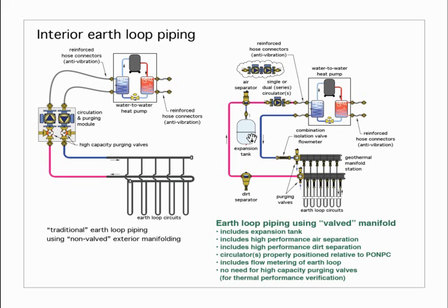So basically comparing these two, you see the difference between a manifolded and what I'll call a fully trimmed system, which is quite honestly very characteristic of systems you'll see in the European market versus the traditional North American approach over on the left. I don't want to knock either one. I simply want to say the one on the right does bring some advantages in terms of hydronics.